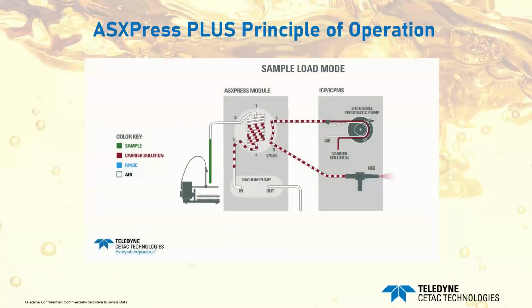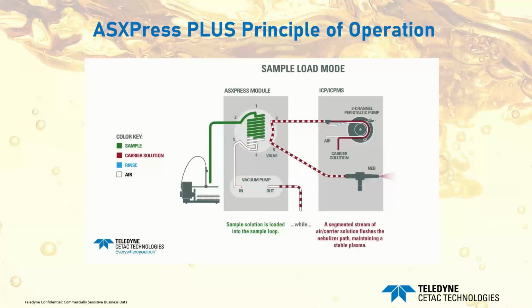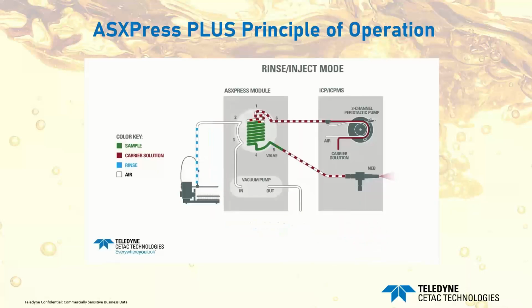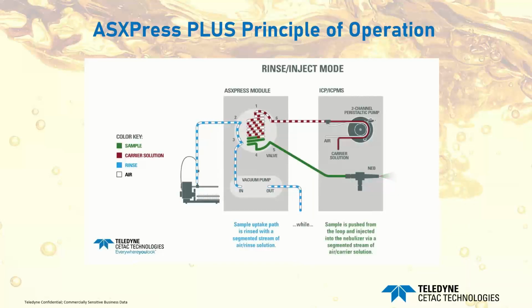And here you can see an animation of the process as it works. You see the green sample going from the auto sampler into the loop, and the vacuum pump is in control of this. So the actual loading of the loop is much faster than what this animation shows. After the loop is loaded, the valve switches and it directs the carrier solution into the loop. Air bubbles are introduced along with this flow. So as the carrier solution is pushing the sample to the nebulizer, it is also cleaning the loop in the process. There's a lot happening at once, and the result is a big time savings.